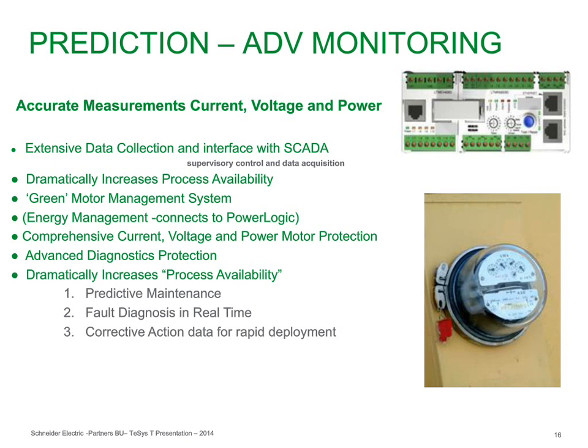So you can actually set, say, an overcurrent alarm on a device that maybe pulls 50 amps. You could set an overcurrent alarm, say, for 65 amps, even though you might set the fault for 100 amps. And if you ever do get a current at 65 amps, the amount of time between it's at 65 to the time it gets to 100 is the amount of time you actually have to do predictive maintenance.